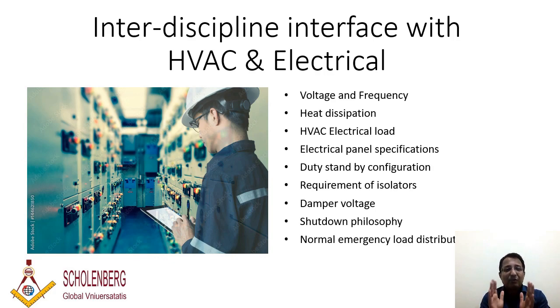Because at 60 Hz, the RPM of the motor is higher, and at 50 Hz, the RPM of the motor is lower. So if you select a motor with the wrong hertz or frequency, the output, whether air or refrigerant, will be different, and it may be over capacity or under capacity. So selection plays a very important role here. These are the two things you need to keep in mind: voltage and frequency. You need to ask them, because based on that your equipment gets selected.